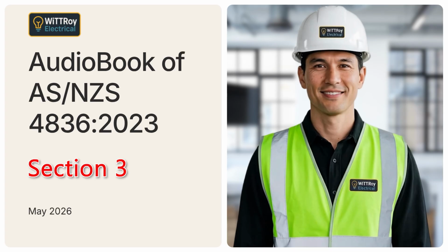3.1.6 Temporary bonding of conductors. 3.1.6 explains temporary bonding of conductors. Where the risk assessment identifies the need for temporary bonding, the conductors must be bonded together and connected to the general mass of earth at the work site. The bonding conductors must be suitable to carry the prospective short-circuit current back to the installation earthing system. The conductor should be flexible and not less than 6 square millimeters. Temporary bonding conductors must always be connected together and attached to earth before they are attached to any de-energized part of the electrical installation.